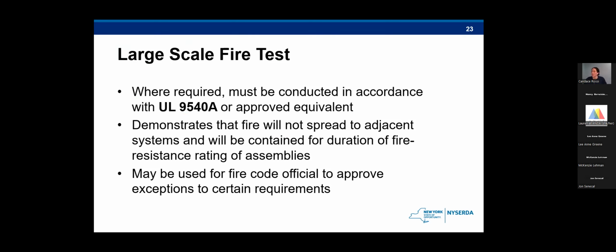And then next we have the large scale fire test. So this is where it's required. Large scale fire testing must be conducted on a representative energy storage system in accordance with UL 9540A or an approved equivalent by an approved testing laboratory. The test must show that a fire involving one system will not propagate to an adjacent system.